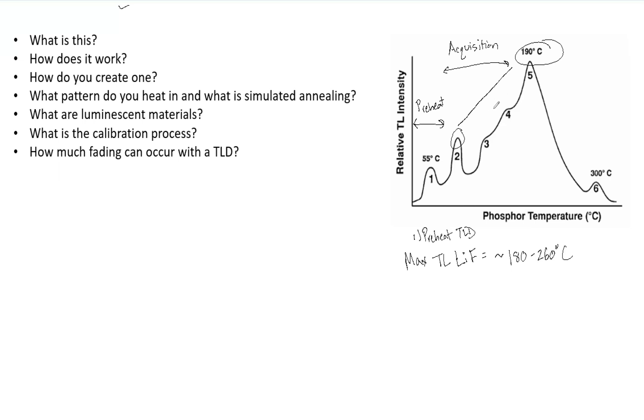It's very important to increase the heat at the same rate. Then once you get to your max thermoluminescence here, now you can rapidly drop off, and so that would be our annealing state. That annealing wipes out any electrons within any of the traps, and then you are able to reuse that TLD.